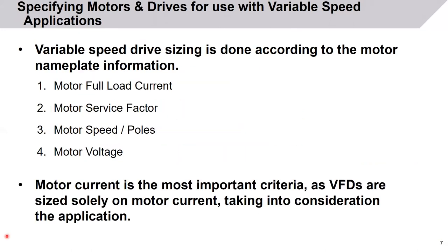Variable speed drive sizing is done according to motor nameplate information: motor full load current (most important), service factor — some companies like to run motors into service factor so that is certainly a consideration — motor speed, and motor voltage. Motor current is the most important criteria as VFDs are sized solely on motor current, taking into consideration the application.